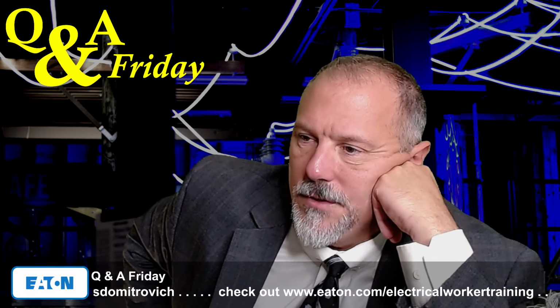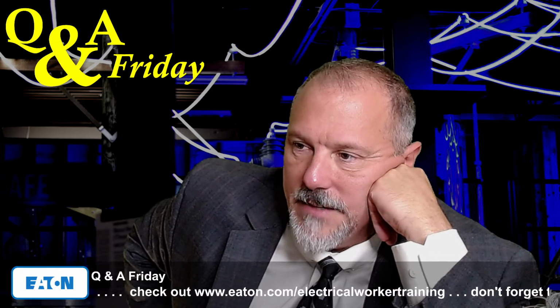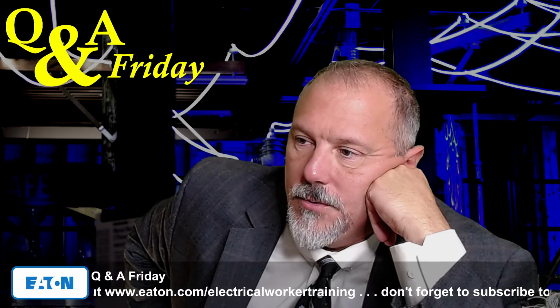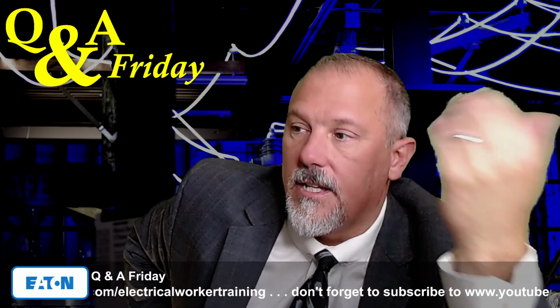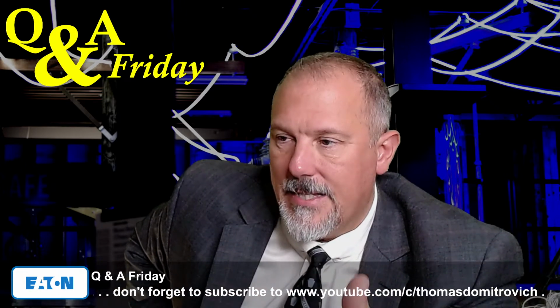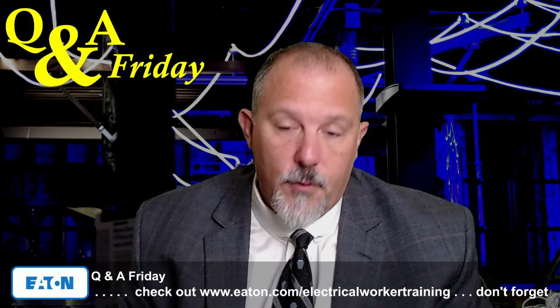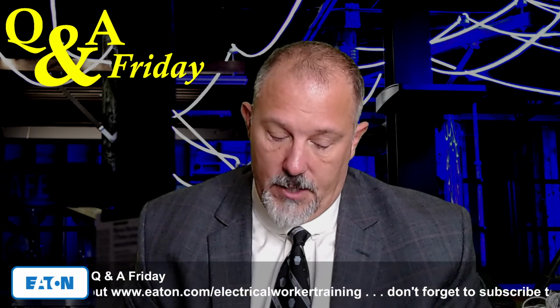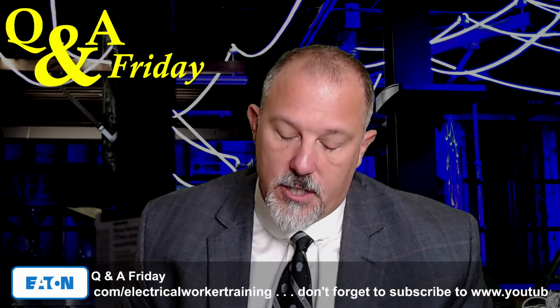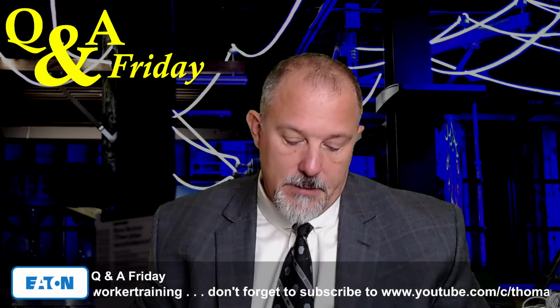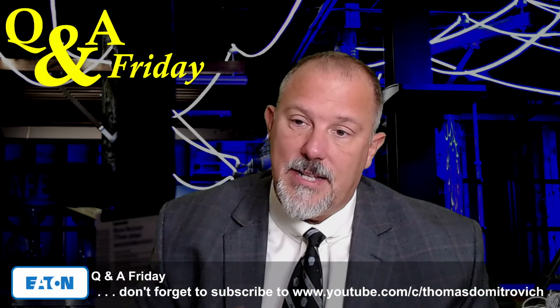Okay, by the newly added 240.67 and 240.87 in NEC 2020, do consumable energy reduction devices like fuses or arc quenchers get wasted in the first performance testing? Or are there any means to ensure the arc energy reduction performance of assembled arc resistant equipment without paying the price twice? What this one is dealing with is 240.87. Remember, we just introduced a requirement that when you do an arc energy reduction maintenance system in 240.87, it has to be performance tested. And 240.67 is the same way.